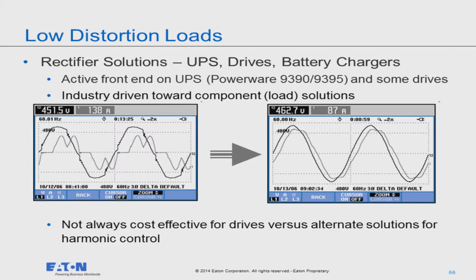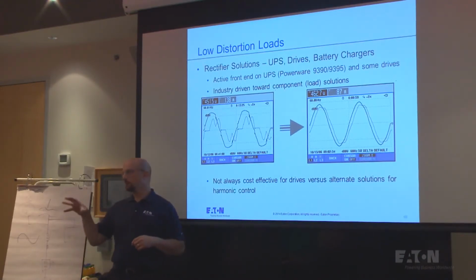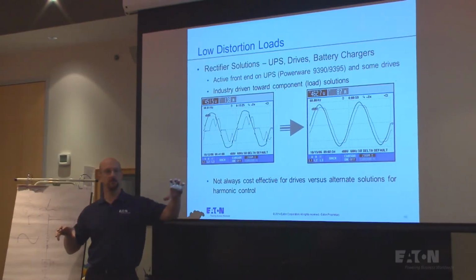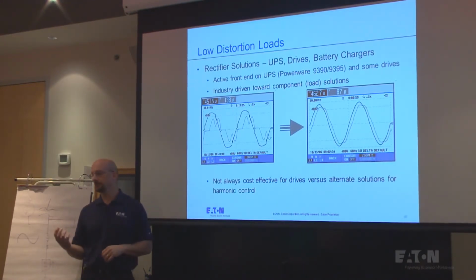Again, what they've done with UPSs is they've put active rectifiers in the front end. So our new 9395, 9390, 93 PM, those are active rectifier UPSs. The rectifier on the front end uses IGBTs, just like the PWM on the output for the UPS or our drives. But they took out this big transformer and a big harmonic filter and replaced the front end of the drive with these IGBTs, okay? So they took out a bunch of cost and physical size and weight and all this other stuff, and they put in an active rectifier.